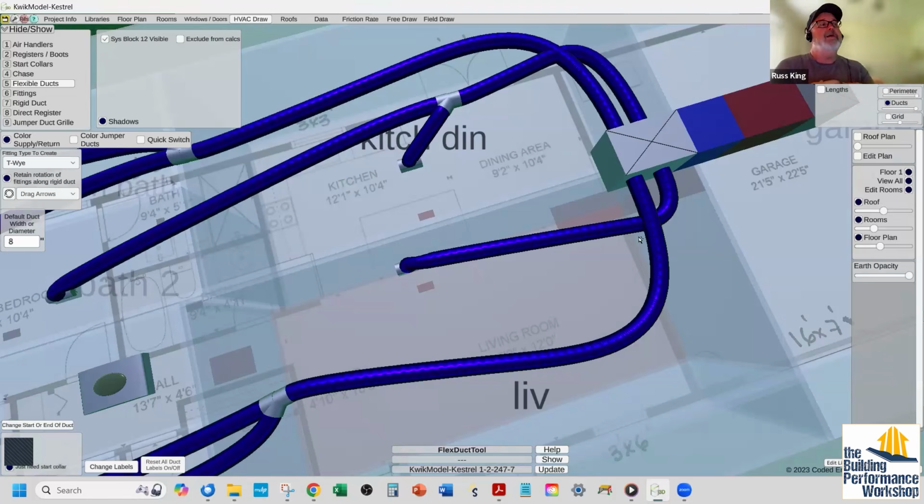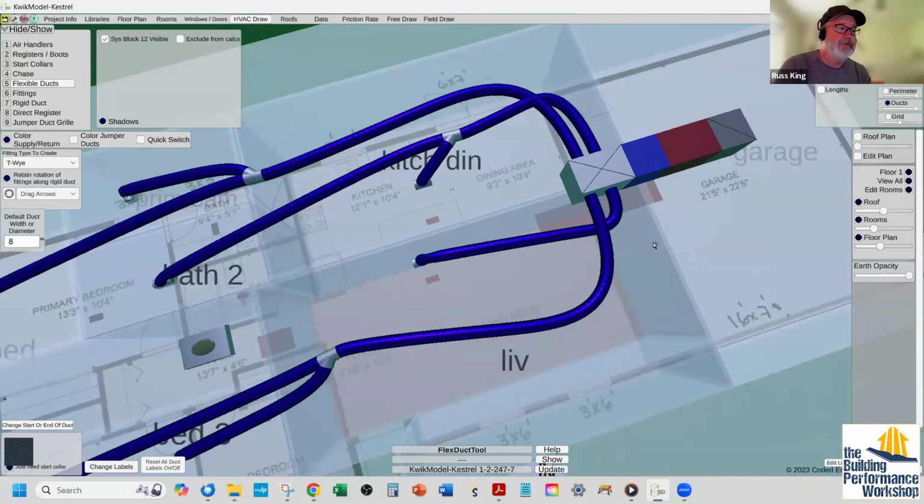But if you want, like I said, predictability, it's the ability to predict the air, and what we're doing is we're sizing ducts to a certain size in order to get a certain amount of air to a room. And if you want that to be predictable, you have to follow certain rules of thumb and certain guidelines and things like that. And a lot of the guidelines are not written anywhere, like the whole thing I just mentioned about being symmetrical and stuff like that.